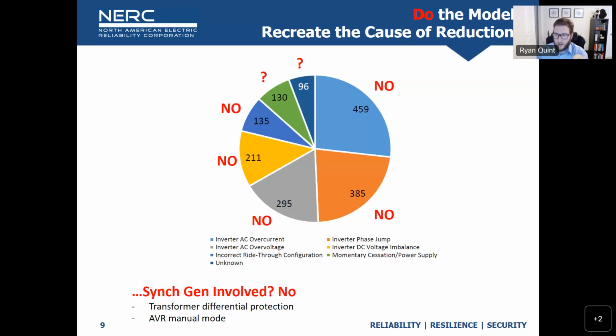It's worth noting that all that synchronous generation we lost is also a big no, because we don't model transformer differential protection in positive sequence transmission planning studies generally. We had a plant in an automatic voltage regulator that had a manual mode instead of automatic, unbeknownst to the plant operator because of some updated AVR settings.